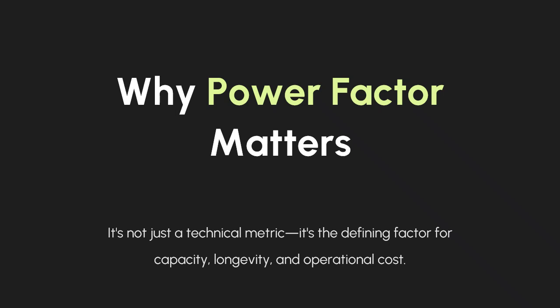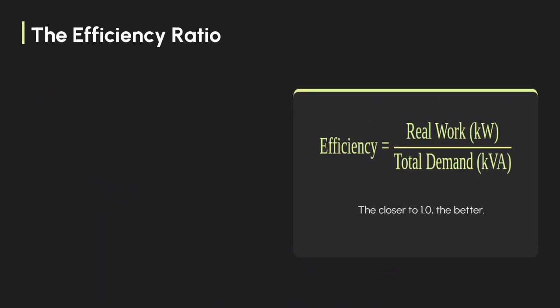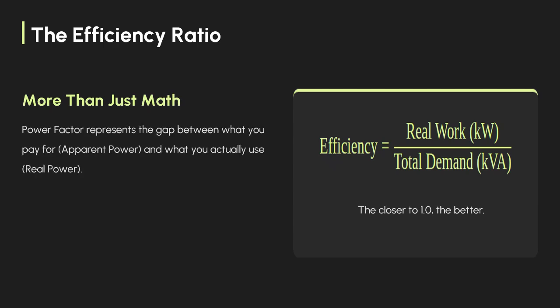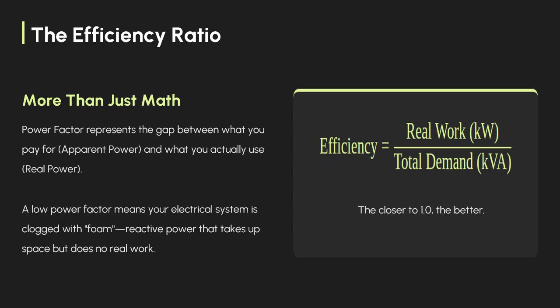The core concept, the efficiency ratio. Let's start with a quick recap. Power factor is fundamentally an efficiency ratio. It measures the gap between the total electricity supplied to your site, the apparent power in kVA, and the actual useful energy that performs work, the real power in kW. As you see in the formula, our goal is always to get this ratio as close to unity, or 1.0, as possible. A low power factor means your system is wasting energy on reactive power that does no real work.